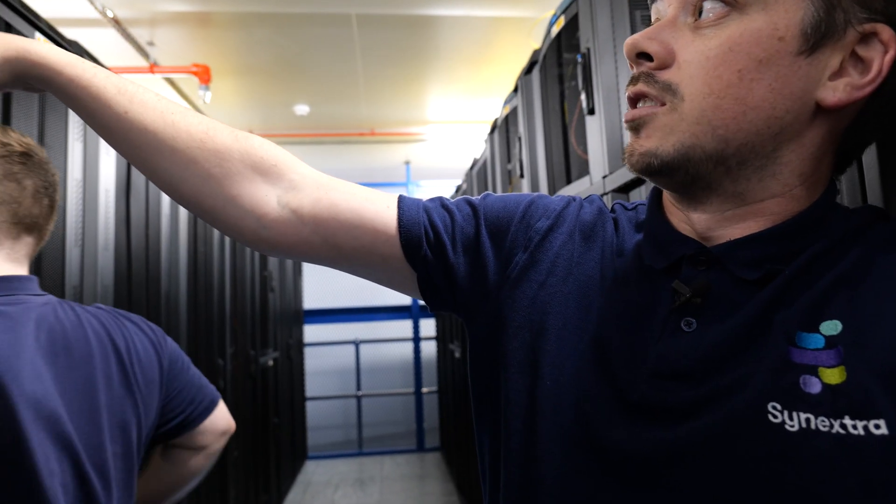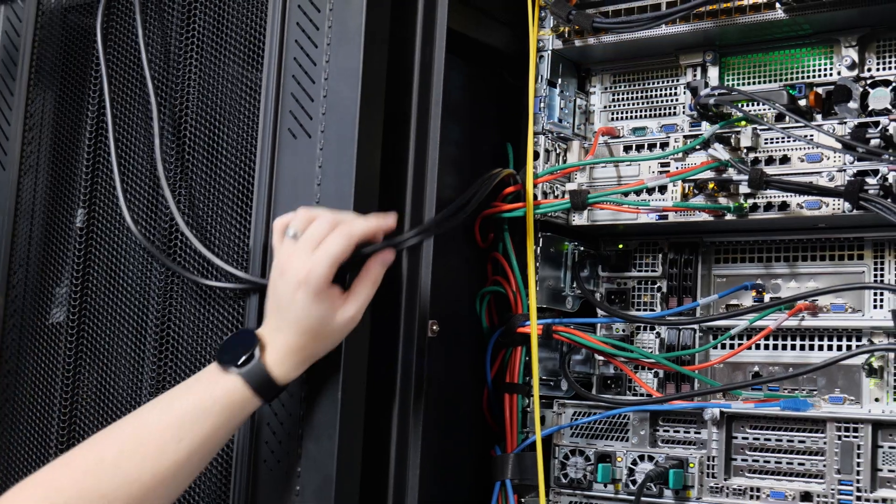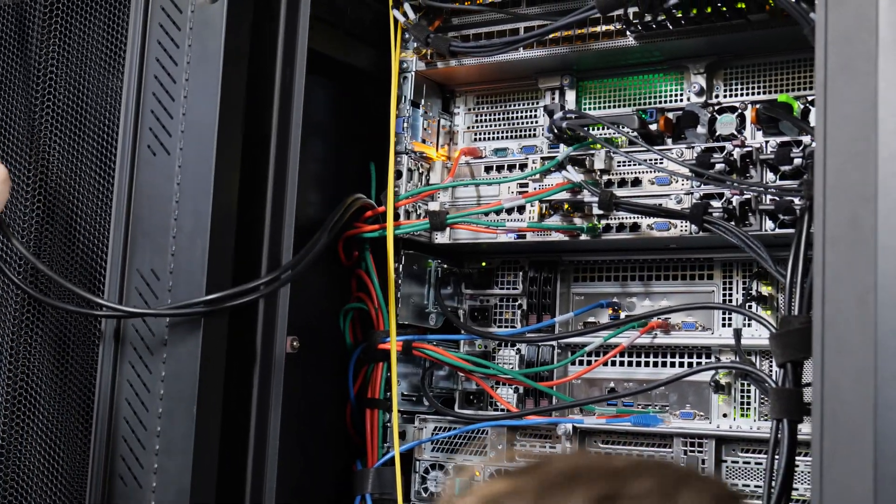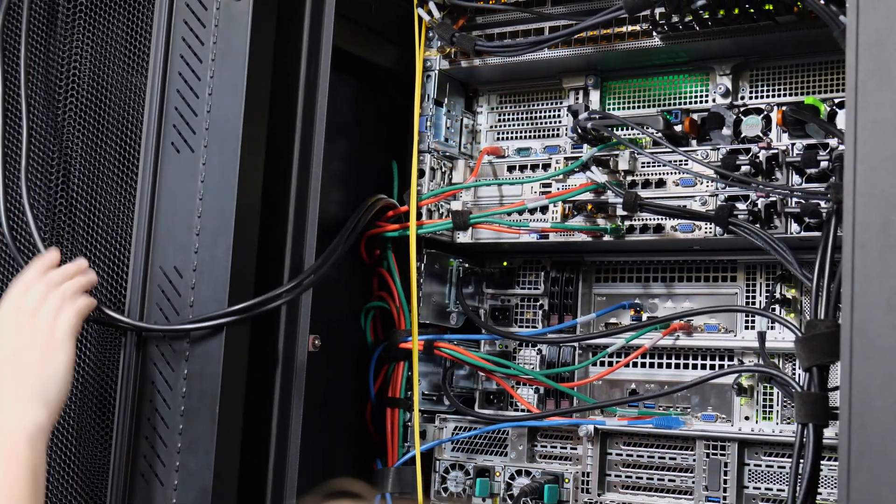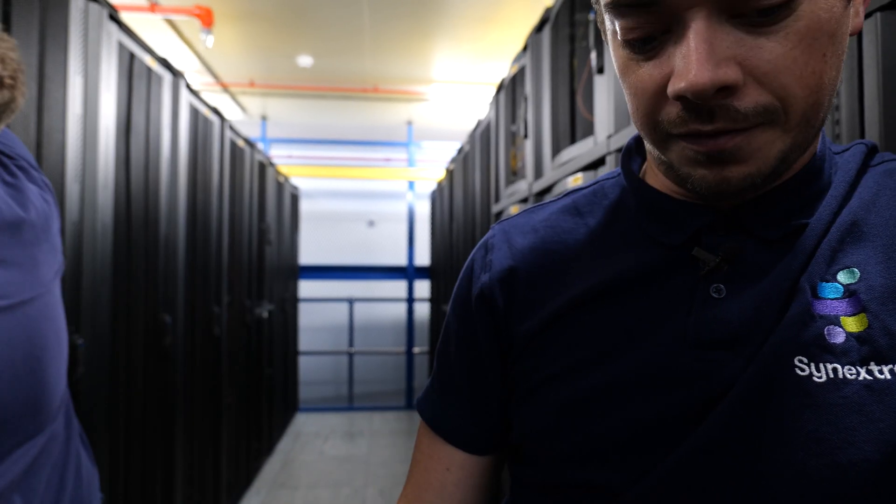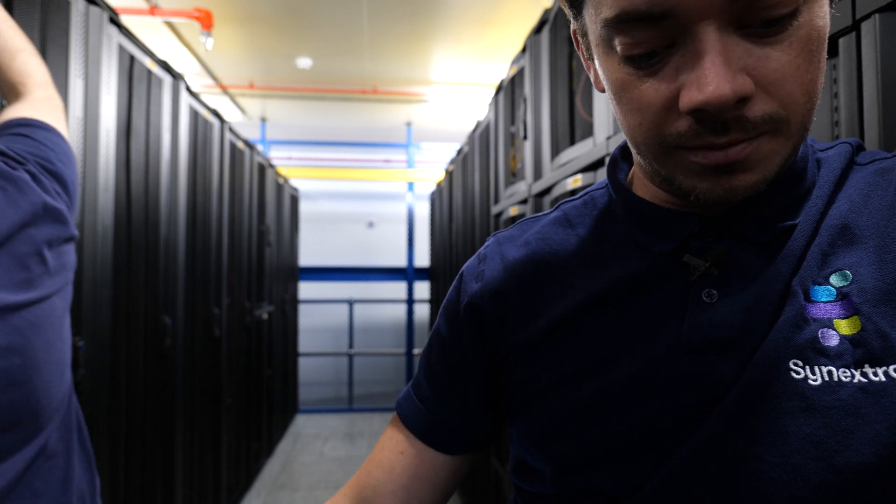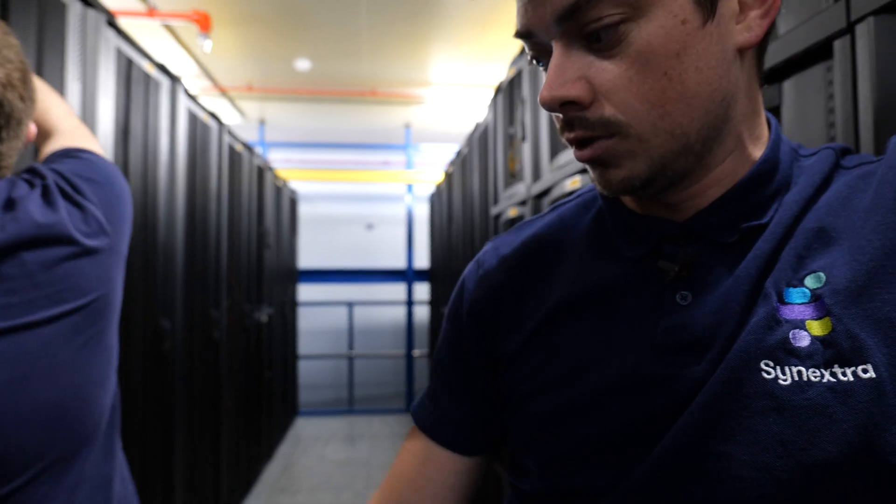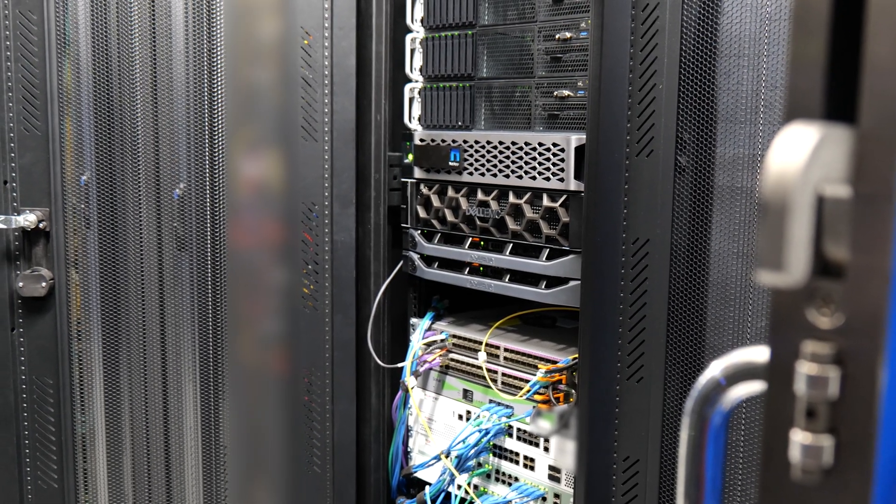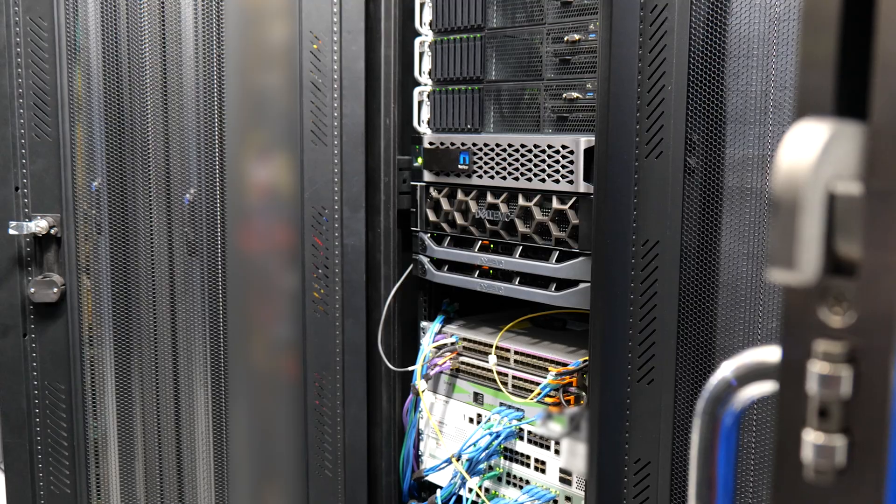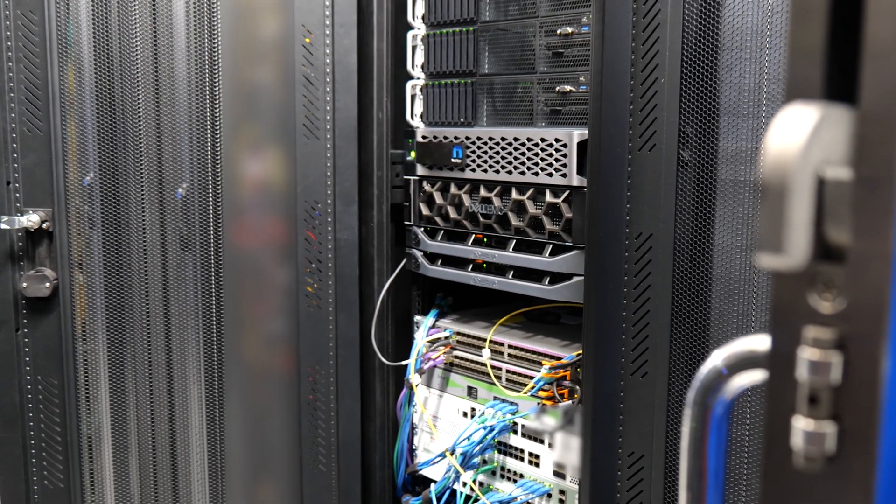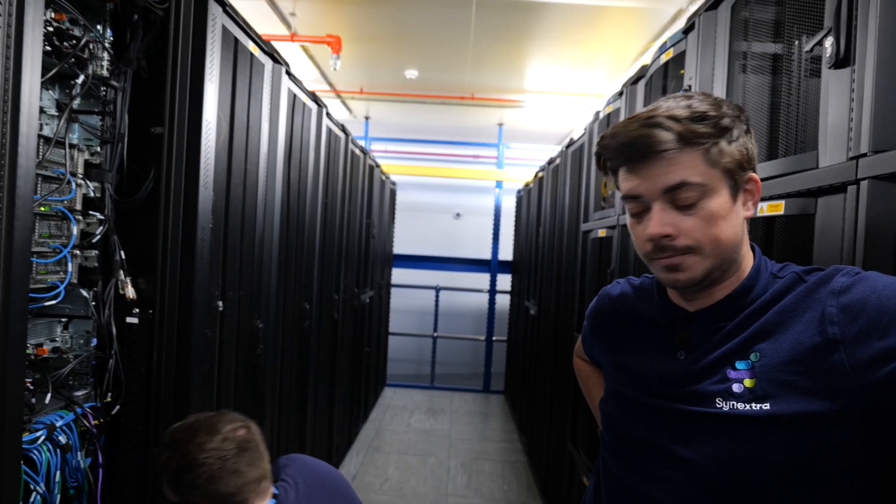All the servers, as you can see, have dual power supply for redundancy. There's two PDUs going into one feed under the floor, so obviously if one goes off, the other one should carry on supplying power, so that everything can run on one cable.